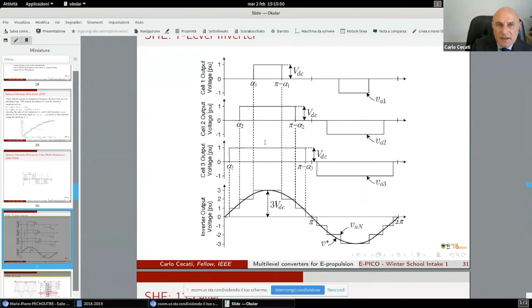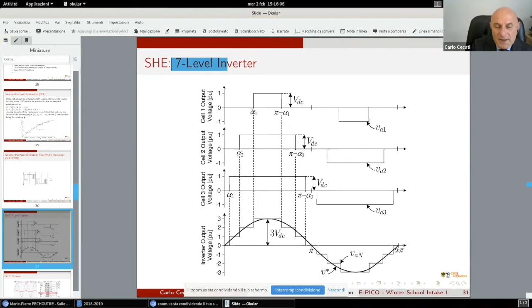So I'll move very quickly. I stopped here just to show how it works in the case of fundamental frequency modulation for a 7-level inverter. Basically, the modulation algorithm computes and identifies the value of angles alpha 1, alpha 2, and alpha 3, so that the output voltage of the inverter is represented by this waveform. As you can see, this waveform is, with some degree of approximation and interpolation, the expected sinusoidal waveform. So the modulation algorithm computes the exact value of alpha 1, alpha 2, and alpha 3.